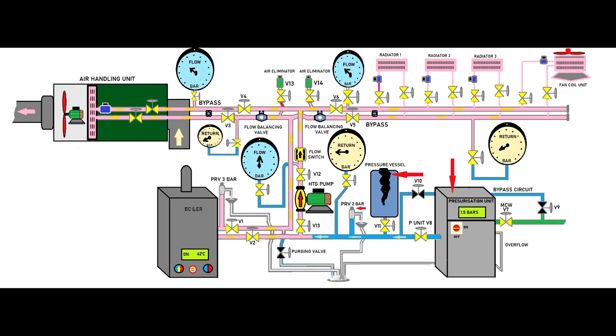And once you do that, the pressure can increase so much. And if the pressure increases, then the pressurization unit will stop the boilers if you reach the pressure limit. So now the high pressure limit forces the pressurization unit to turn off the boiler for safety reasons. And now the entire building will freeze because of a simple fault like the pressure vessel rubber bellow. The pressurization unit has the high limit set below the pressure release valve high limit, so it cuts the boiler before the PRV reaches its higher limit.